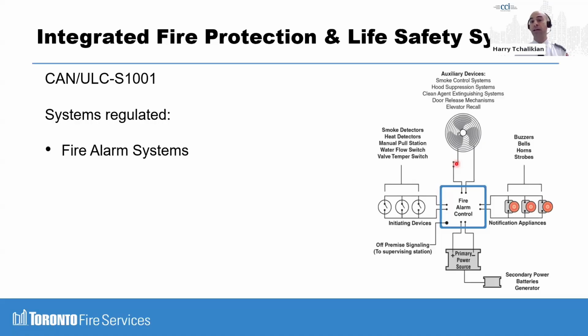In your fire alarm test, they would just account for the fact that it's working up to that relay. What happens downstream of that relay? Did the smoke control system operate? Did the hood suppression system communicate, operate? Did the clean agent extinguishing system turn on? Door release mechanisms, elevator recall is a big one. With this integrated systems testing, we'll get to the frequency, but now you have to make sure that nothing has fallen between the cracks. The good news here is you're probably already doing 90 to 100% of this, depending on your building. What we're doing with this is now just making sure that nothing fell between the cracks here. And so we'll go over some details.